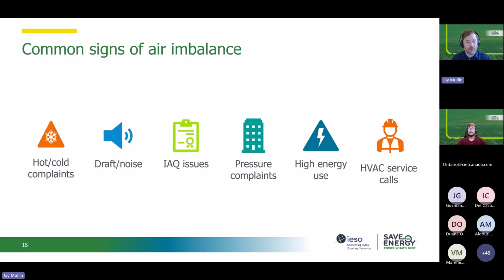If there's high energy use from fans, or trending data shows that your fans are running harder than they should be, your exhaust or ventilation fans. Also, if you have recurring HVAC service calls for similar issues over and over, that could indicate that there's additional unnecessary stress on some of those components of your systems. So all these can give clues that there is a pressure problem, and it might be worthwhile undertaking an air balance study. If anyone has any questions or comments or experiences they'd like to share, please do so in the chat as we're going through this.